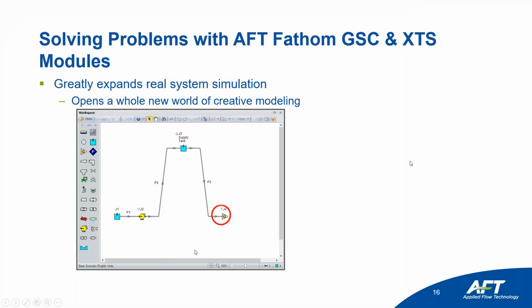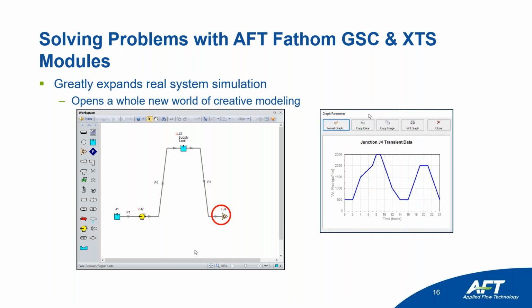so down in the bottom, I have an assigned flow junction, okay? So my assigned flow junction, that specifies a flow set point at that location. The way that Fathom does that is it changes the pressure at that junction in order to give you the flow rate that you want, okay? That's steady state. But when you turn on the extended time simulation module to do a transient simulation, what you can do is specify a transient flow profile over time.